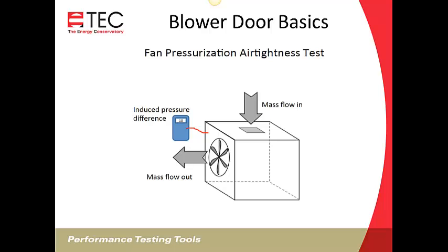So that's the essence, really, of a blower door test. The airflow that's coming out through the fan, an equal amount must leak in. So whenever you turn on a fan, an equal amount is leaking in instantly, or almost instantly. And we wanna be displaying the induced pressure difference. If you're in an area where it's always 75 degrees inside and 70 degrees outside and it's never windy, then baseline isn't as important. But the colder and windier your climate is, the bigger effect it's going to have.